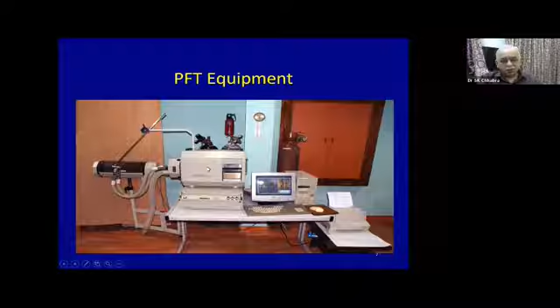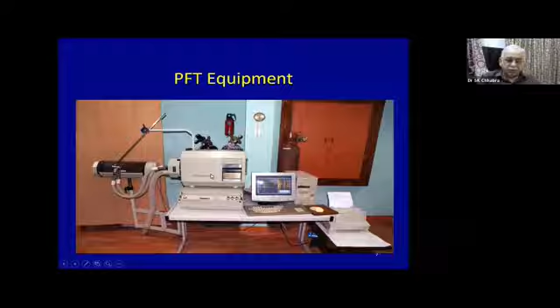So the patient is breathing in and out, and how much he breathes in, we measure by the displacement of the drum, which is inside this. So this is a volume spirometer. Normally volume spirometers are big, bulky, but they are more sturdy and they maintain their calibration for long. These used to be very popular once upon a time, but gradually we have shifted over to flow measuring devices.